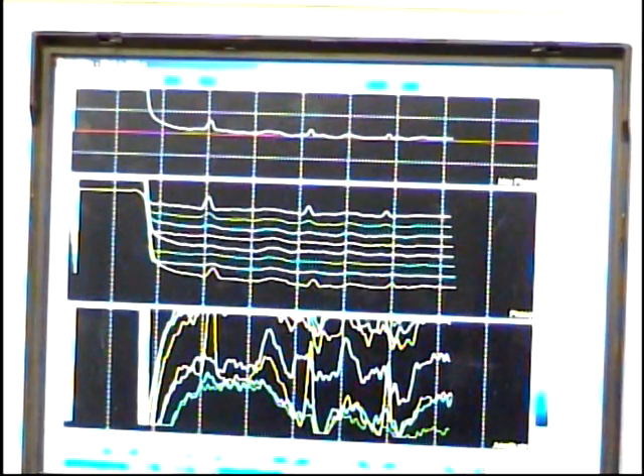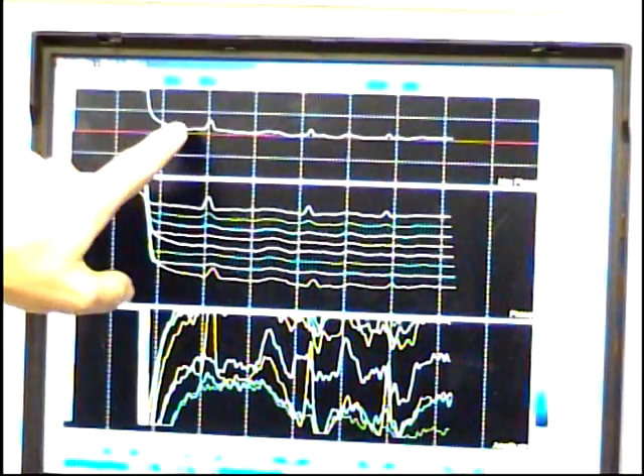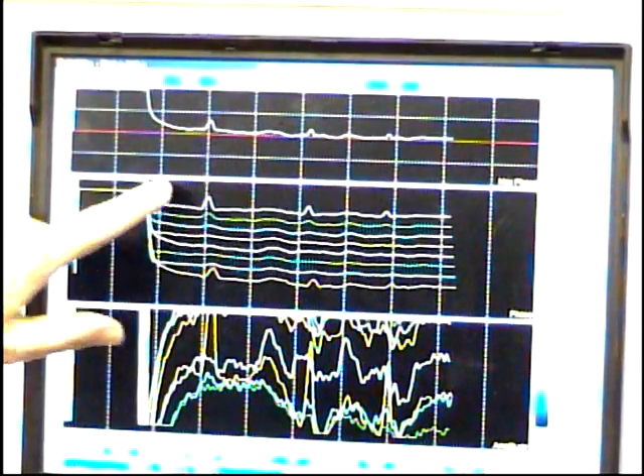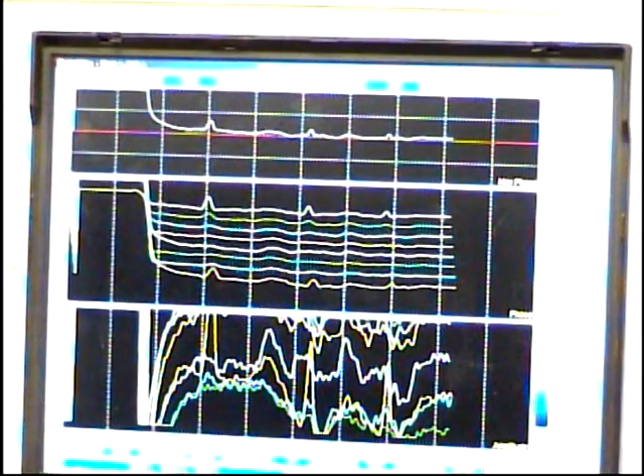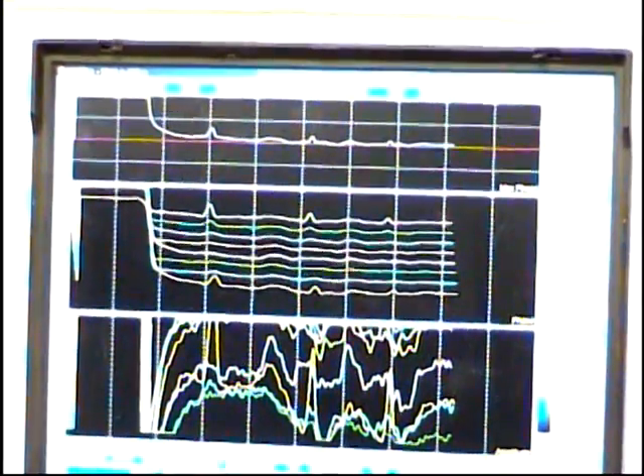Hit the pause button. And notice this is what it would look like in single channel. This is all 8 channels. Remember, we have 8 sensors going around. Now keep in mind that with the remote field system, we cannot distinguish whether it's ID or OD. But we can give you a location.